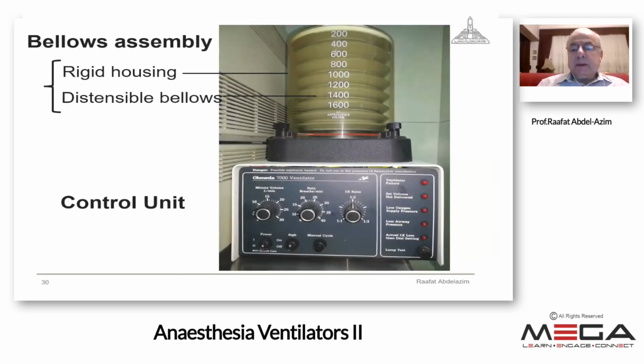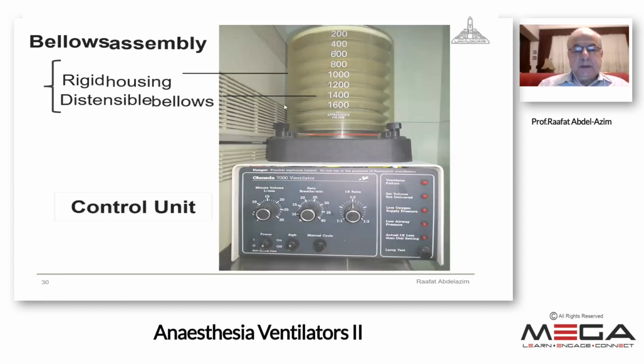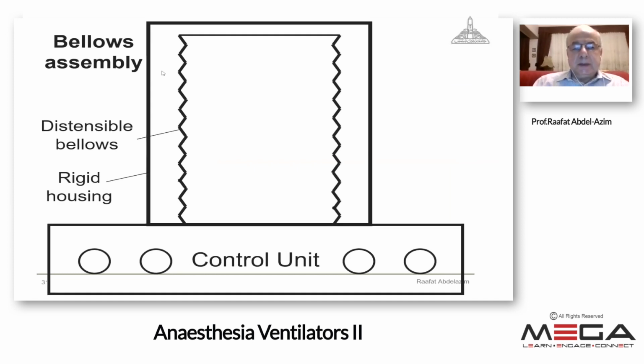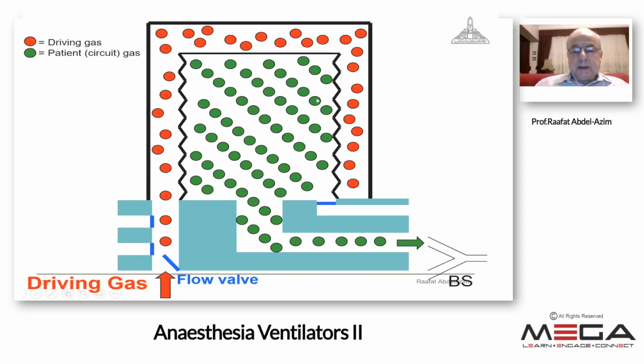The ventilator, the traditional or the ascending bellows, consists of control panel and bellows assembly. The bellows assembly is a rigid, transparent housing containing the bellows. The patient gas is the gas coming from the patient's lungs through the expiratory limb to expand the bellows, and that is again compressed down to be pushed again into the patient's lung.